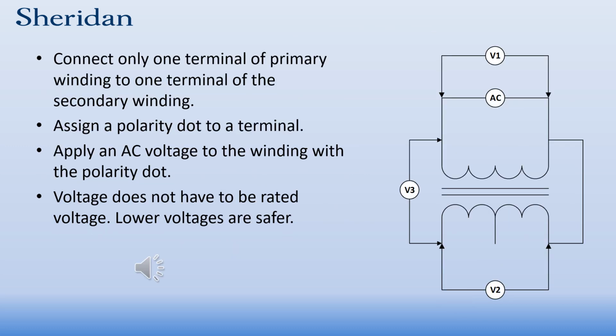To begin with, to do the polarity test, we connect one terminal of the primary to one terminal of the secondary. That puts the two windings in series, and we assign a polarity dot to one of the terminals on the primary. You should always apply your test voltage to the high voltage side. Remember, that can be determined by which winding has the highest ohmic value. Okay, so apply an AC voltage to the winding with the polarity dot. However, this voltage does not have to be rated voltage. It's safer to use a voltage that is lower than rated voltage.